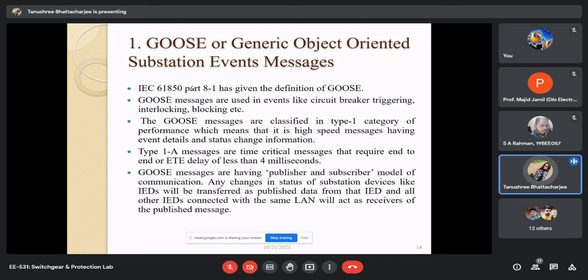Why? Because as said before, IEDs can communicate with each other. Meaning, in one bay, however many IEDs are installed, think about a complex and big substation, not a smaller one like in the lab, so there many IEDs are connected to a bay controller. So if one circuit breaker is switching, there can be an overloading of a line because of a fault, and that overloading can create another fault in another line due to overloading, right? So that situation can be handled with this GOOSE message. What it does is, when any one of the IEDs gets a fault signal, it will communicate easily to the other IEDs of the same bay unit. So they will understand that there is a fault in a line, so you need to shift the load to another line, or you need to shed the load, meaning load shedding.